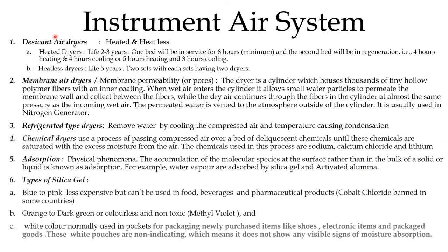Now we can see some important definitions used in instrument air dryers. The instrument air dryer is of two types: heated type and heatless dryer. Heated dryer media life is two to three years. One bed will be in service for eight hours minimum, and the second bed will be in regeneration — either four hours heating and four hours cooling, or five hours heating and three hours cooling. In heatless dryer, media life is more — up to five years. Two sets with each set having two dryers are used in heatless dryers.